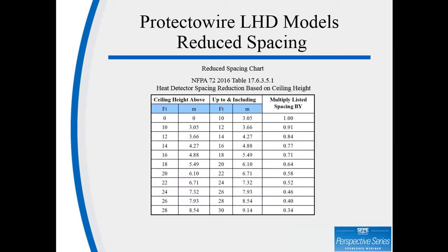NFPA 72 requires that all heat detector spacings be reduced based on ceiling height. This chart shows the reductions and the percentage reductions that can be applied. Because we have FM and UL, and those spacings are different, FM is 30 feet on centers for most detectors, and UL is 50 feet on centers for most detectors, they have to be applied to this chart. At 10 feet, we can use the listed spacing, FM 30, UL 50. But as we go higher, and the ceiling height goes up to 28 to 30 feet, we can only use 34%. The spacing has to be reduced down to 17 feet for UL and roughly 10 feet for FM.